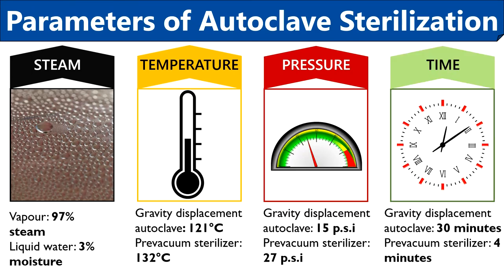Finally, the steam penetration into the objects placed inside the autoclave increases, which is necessary to kill microorganisms. The last factor is time. A gravity displacement autoclave takes 30 minutes and a pre-vacuum sterilizer takes 4 minutes to destroy microbial cells. Sterilization time may differ depending upon the type and load of contents. Autoclaves are recommended best that use high temperature and short sterilization time.